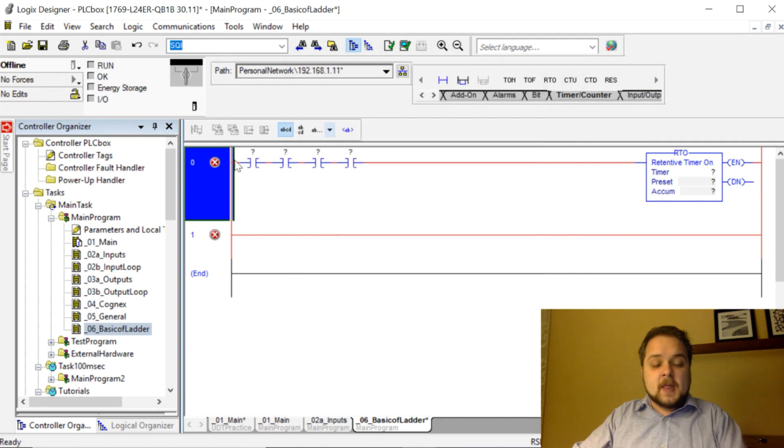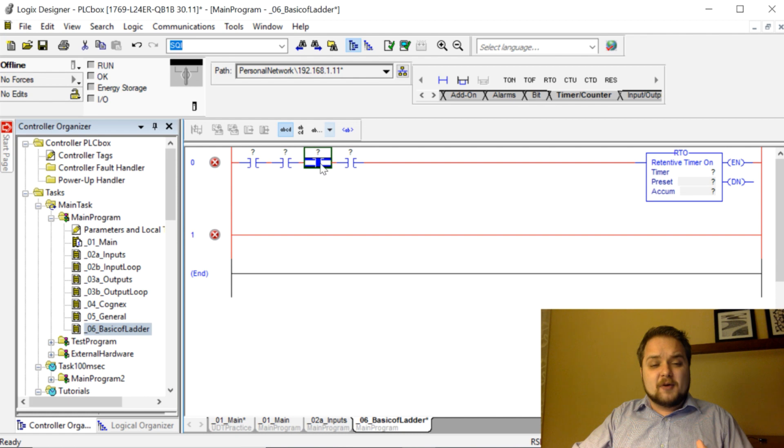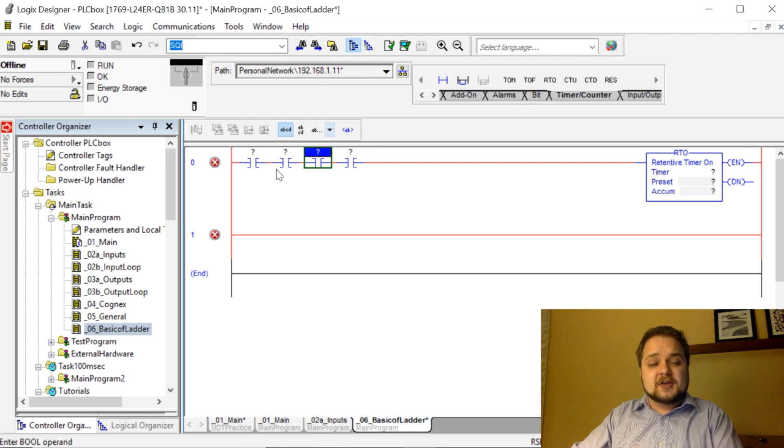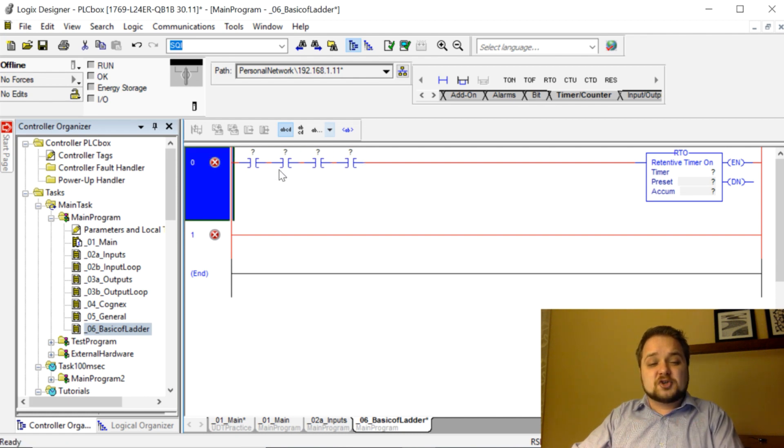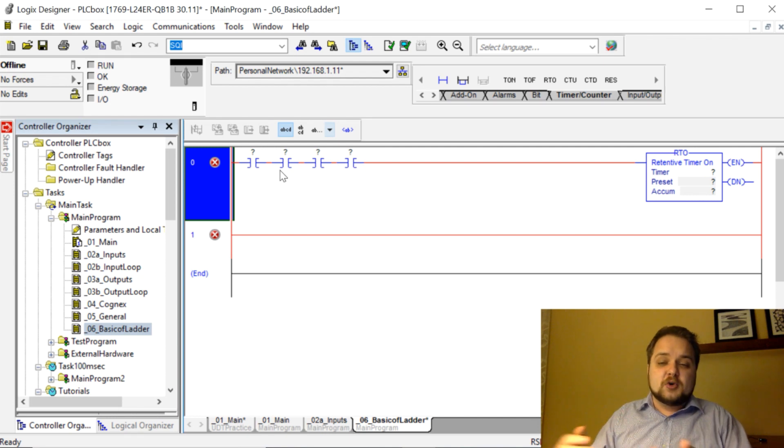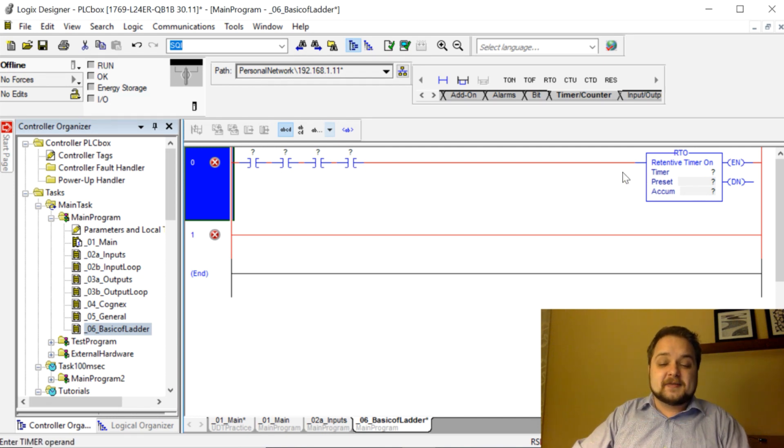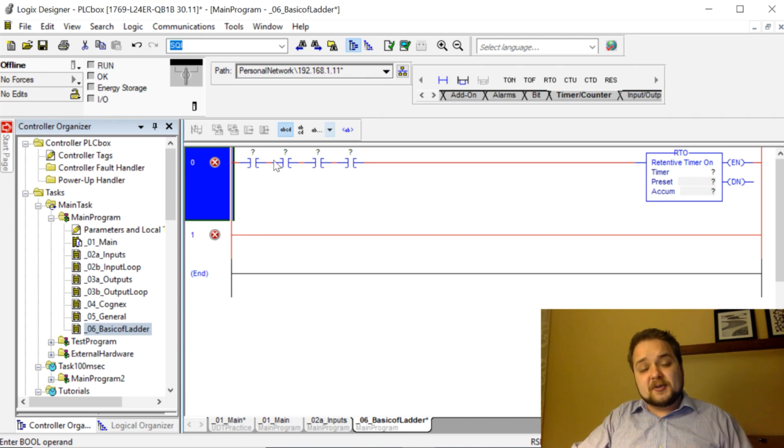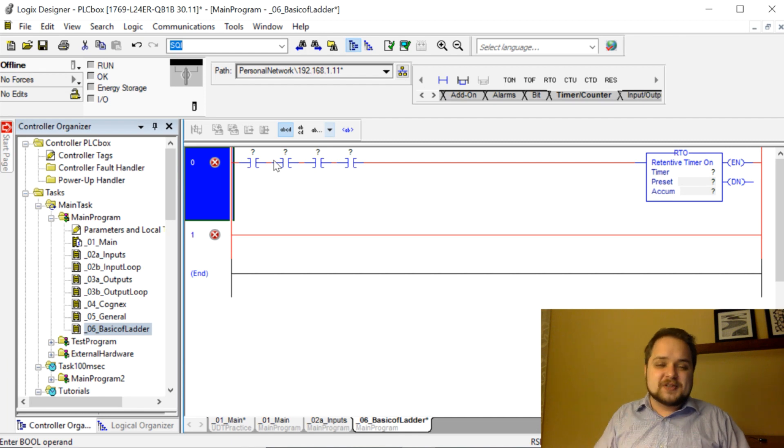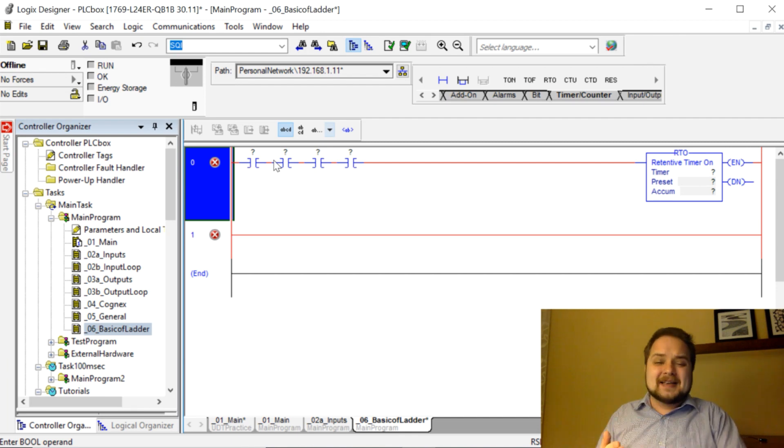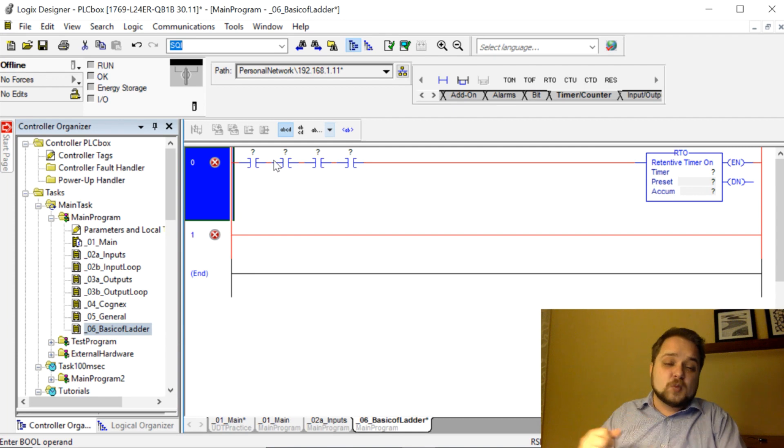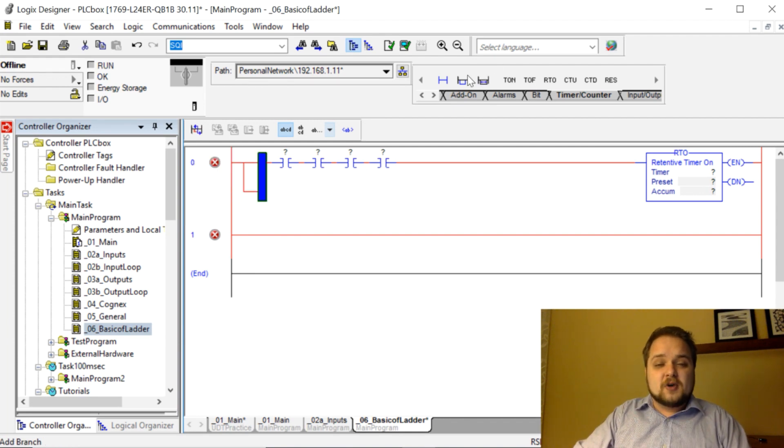There's going to be four instructions in this case. If they are placed in series with each other, just like an electrical circuit, you would need all four of those conditions to be true in order for the retentive timer to be executed. This translates—if you're familiar with other programming languages—this is an AND instruction. So this one AND this one AND this one AND this one need to be true in order for that to execute.